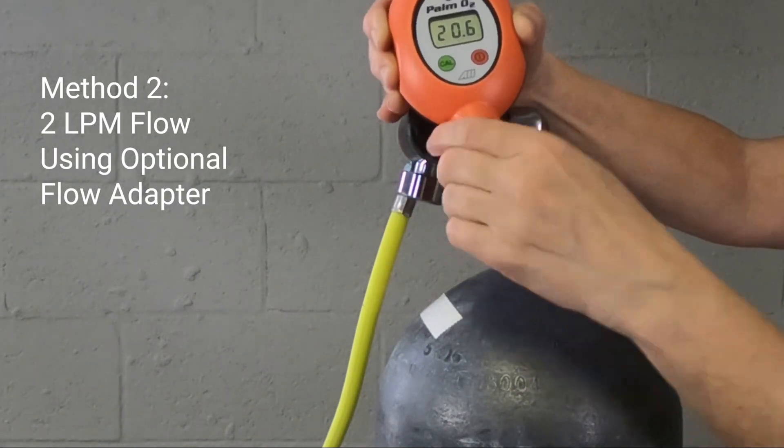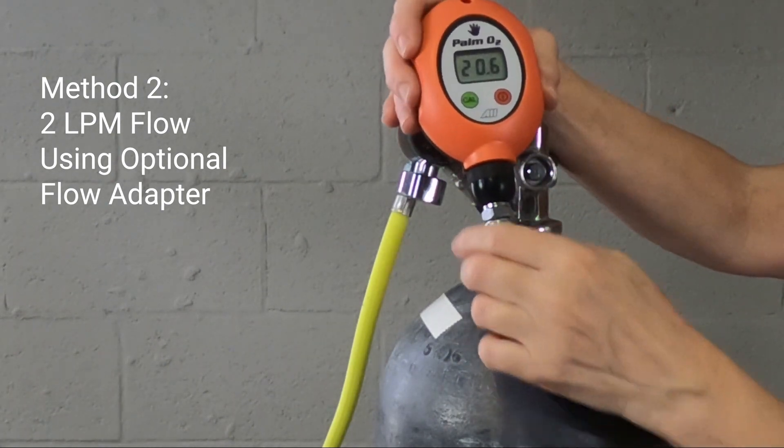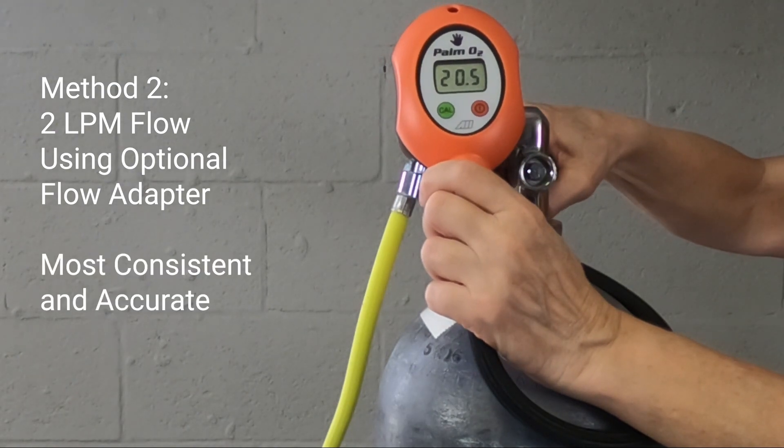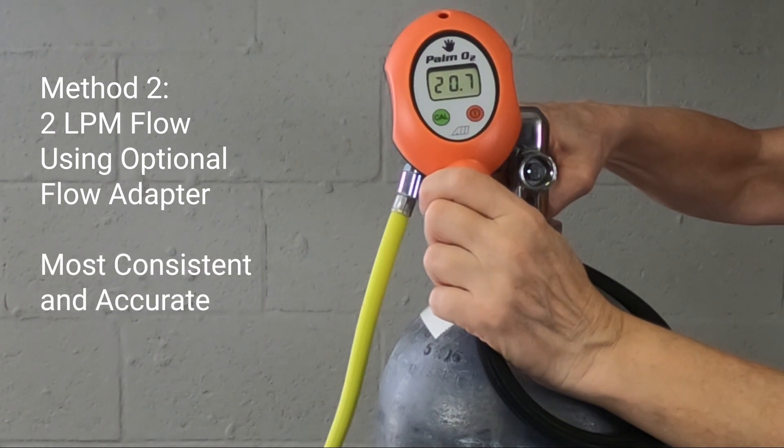The second method is analyzing with a precise 2 liter per minute flow of gas using the optional flow adapter. The flow adapter provides the most consistent and accurate analysis.